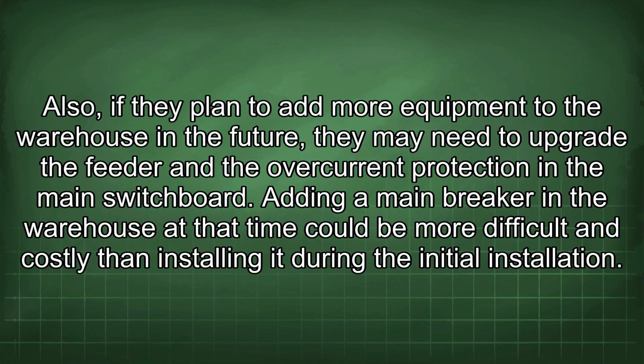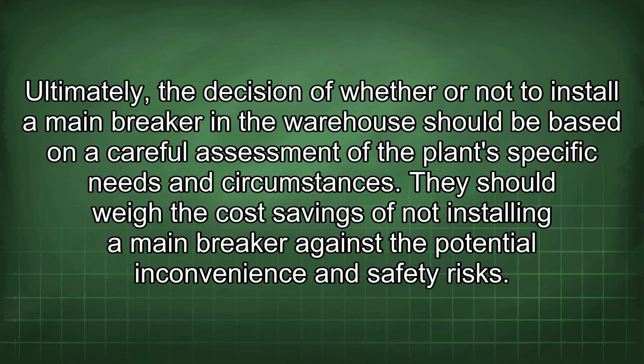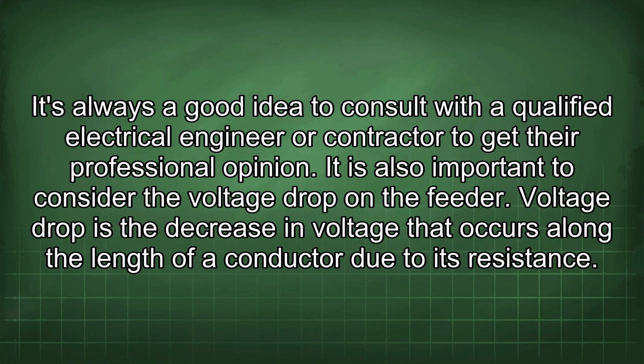This could delay the troubleshooting process and potentially disrupt operations. Also, if they plan to add more equipment to the warehouse in the future, they may need to upgrade the feeder and the overcurrent protection in the main switchboard. Adding a main breaker in the warehouse at that time could be more difficult and costly than installing it during the initial installation. Ultimately, the decision of whether or not to install a main breaker in the warehouse should be based on a careful assessment of the plant's specific needs and circumstances. They should weigh the cost savings of not installing a main breaker against the potential inconvenience and safety risks. It's always a good idea to consult with a qualified electrical engineer or contractor to get their professional opinion.